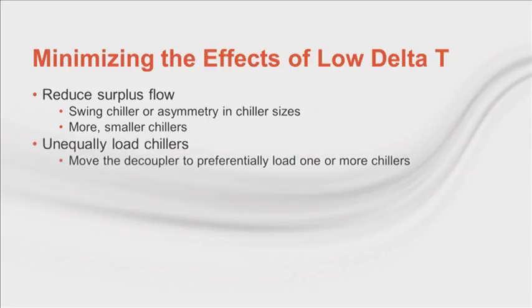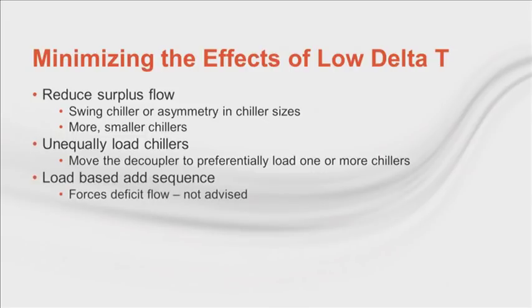Another option is to preferentially load 1 or more of the chillers, with the remainder of the load handled by decoupled chillers, either in parallel or series with a preferentially loaded chiller. Now this means moving the decoupler pipe. One variation I've heard about is to use a load-based add sequence. This is essentially a variation on chilled water reset. The chiller is not added until the building load says that the loads are high enough to need it. With the flow imbalance, this then leads to deficit flow and warmer than generated water being circulated to the loads. We save primary pump energy and delay a chiller start, but the chillers are wasting energy, making the water colder than it will be circulated. Plus, with the warmer circulated water, we use more secondary pump energy.